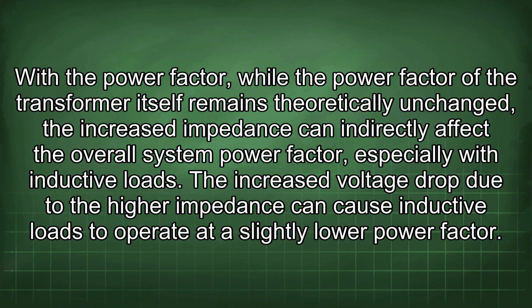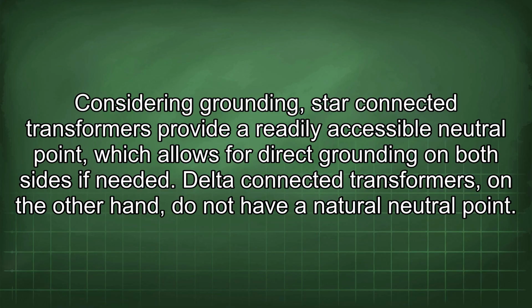With the power factor, while the power factor of the transformer itself remains theoretically unchanged, the increased impedance can indirectly affect the overall system power factor, especially with inductive loads. The increased voltage drop due to the higher impedance can cause inductive loads to operate at a slightly lower power factor. Considering grounding, star-connected transformers provide a readily accessible neutral point, which allows for direct grounding on both sides if needed.